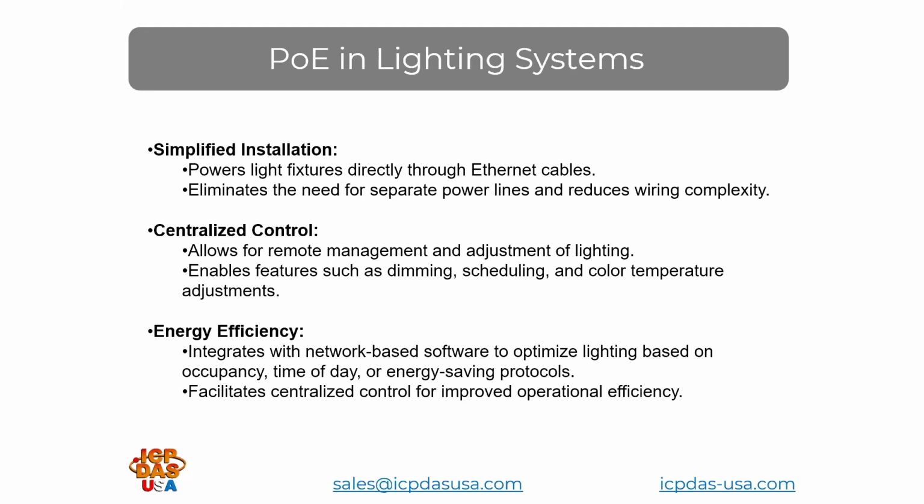for occupancy. You can use controllers to determine if someone's in the room. If no one's in the room, you could turn the lights off or dim the lights. And then when occupancy is detected, you can brighten the lights and leave them on for a few minutes, and then shortly after that, cut power or dim them again.